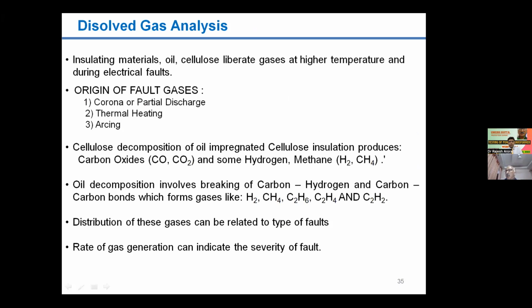So as I said earlier, when there are some issues with the transformer, simply the electrical testing may not suffice. Many times we go for the dissolved gas analysis to conclude whether there are some issues. Sometimes later on we will discuss in detail what kind of gases are formed inside the transformer if there are some issues. So those gases are measured, and accordingly the results of the DGA are checked in light of the electrical testing, and accordingly the inferences are drawn to check whether some issue has taken place inside the transformer.